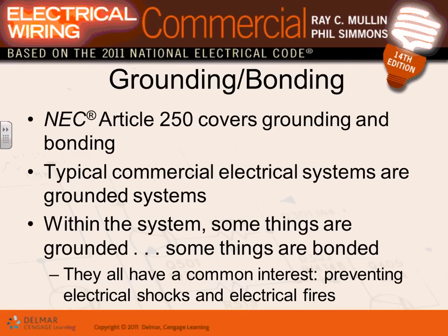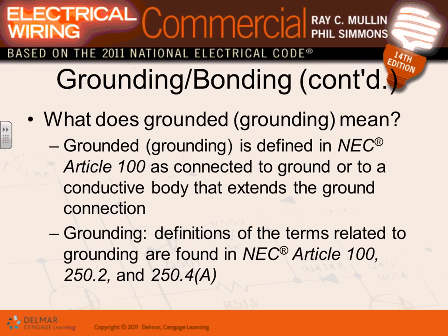So to minimize all this, guys, we send a conductor called the equipment grounding conductor with all the branch circuits and feeders. And so that's grounding the equipment. Then we also ground the system. The system that comes to the building is required to be grounded, most of the buildings. So we take one wire from that transformer and we tie it to the ground to reference ourselves to the ground for safety reasons. So that's probably the most important thing. I'll talk in detail about the sizing when we go to the commercial industrial.